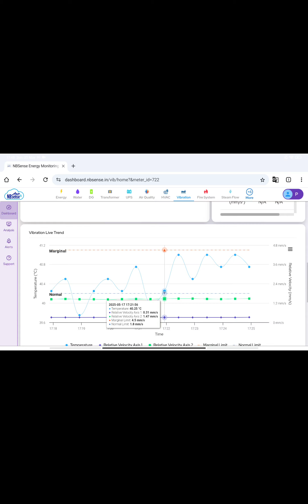Then we have the vibration monitoring. Here we can see all the vibration sensors. We can edit and set their limits. This is designed as per ISO 10816, which is a vibration standard for rotating machinery. We can see the parameters of any individual vibration sensor. We are generally monitoring relative velocity and acceleration on three axes X, Y, Z. Here we can see the values. If these cross the marginal or critical limit, we will get a pop-up. Day wise and month wise mean, max and average are available.